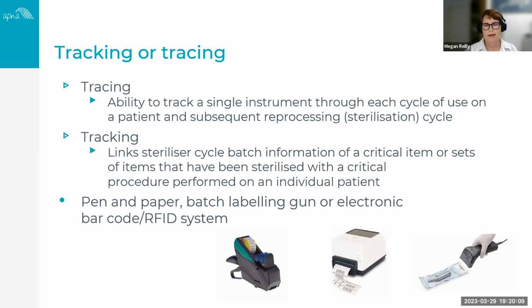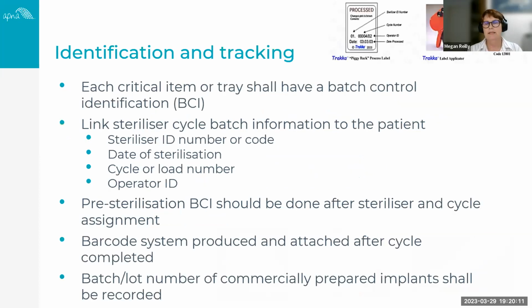But it is important that we can identify and track each critical reusable medical device. Semi-critical devices aren't required to be identified and tracked. However, it is good practice to do that. And certainly it would be reassuring for those of you who are using reusable vaginal speculums, as the patient, I would like to know that that's being identified and tracked in the event that there was a sterilisation process failure.